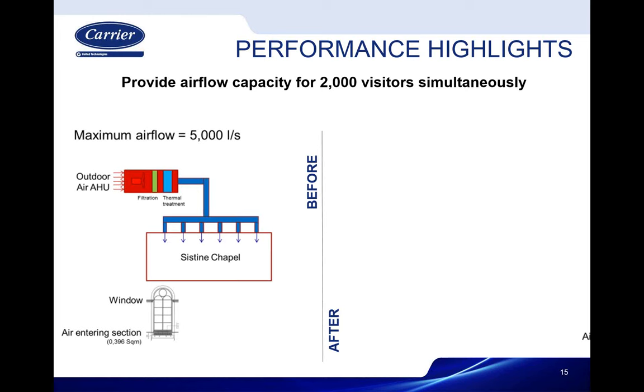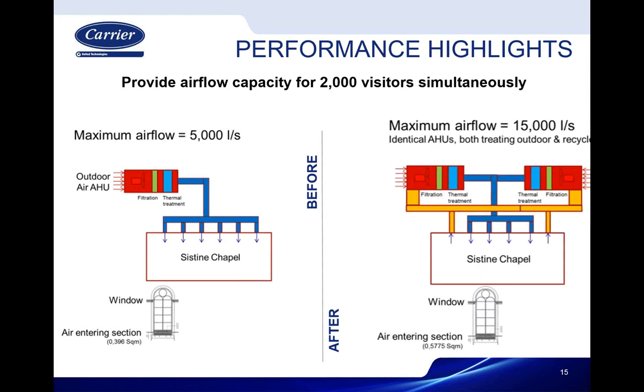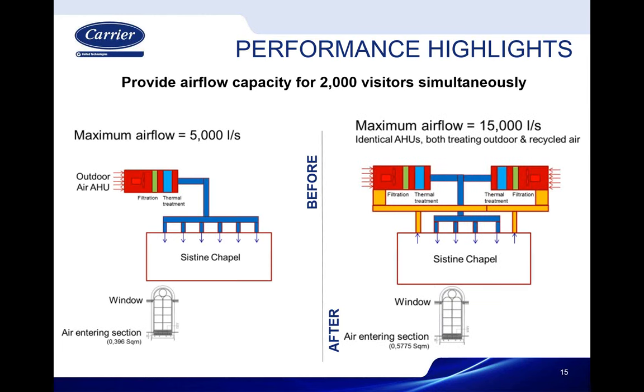It just let the air go, and it essentially exhausted into other parts of the museum complex. Now, on the new system, we've doubled everything. We took away two of the supplies and put in returns so we could have recirculation. We've cross-connected everything so that if we lose any one major component on the left-hand side or the right-hand side, we can keep anywhere from 50 to 70% of the total capacity still active.